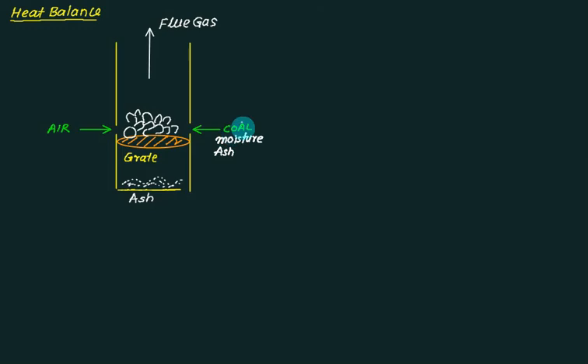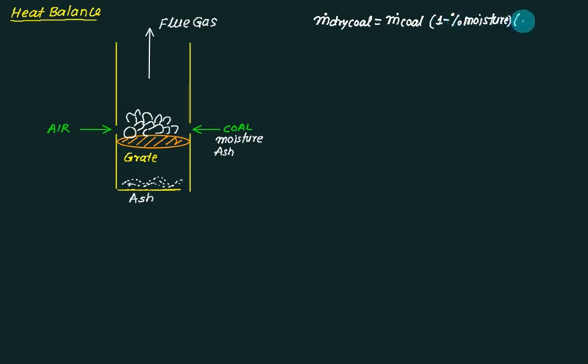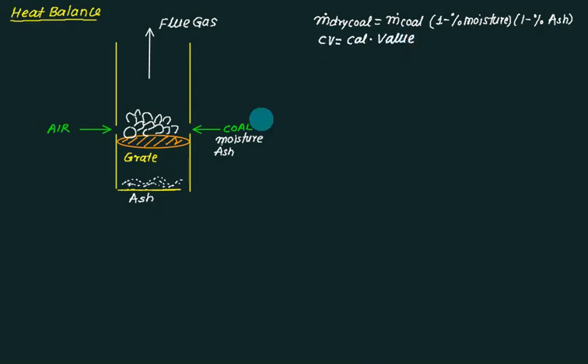Only the dry coal will get burned. The mass of dry coal equals mass of coal multiplied by (1 minus percentage of moisture) multiplied by (1 minus percentage of ash). If CV is the calorific value of the coal, the heat input Q_in equals mass of dry coal multiplied by calorific value — that is equation number one.